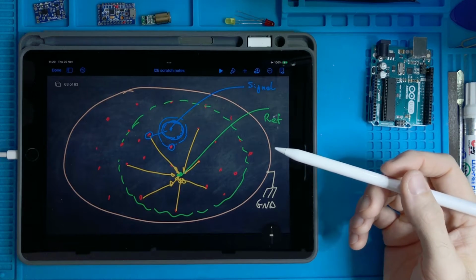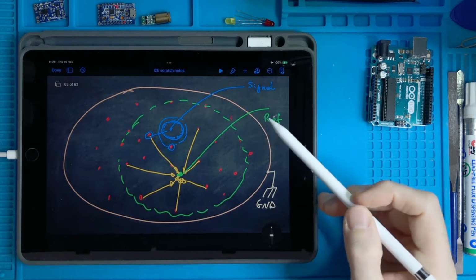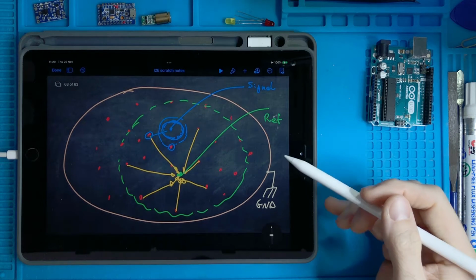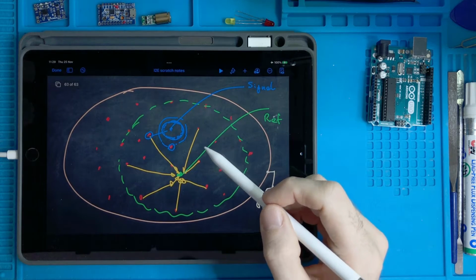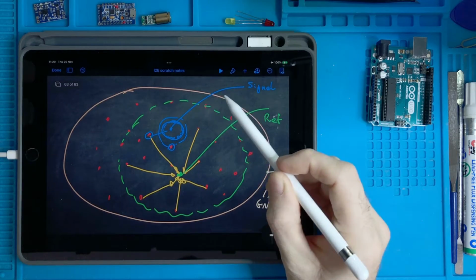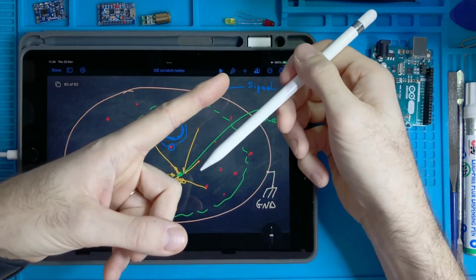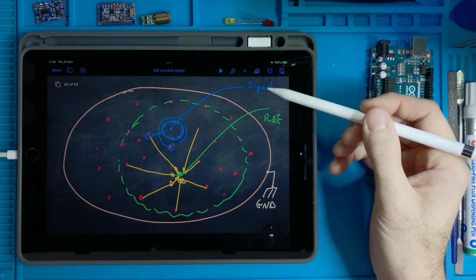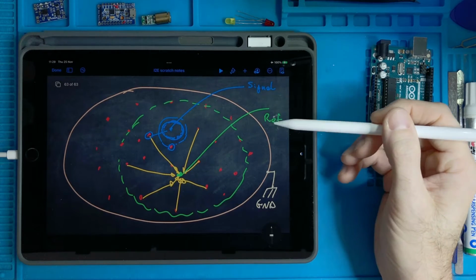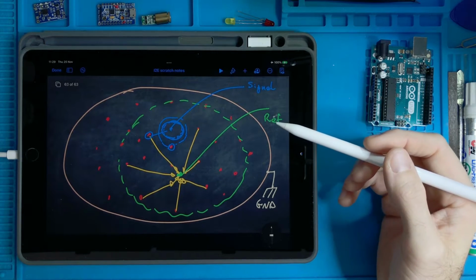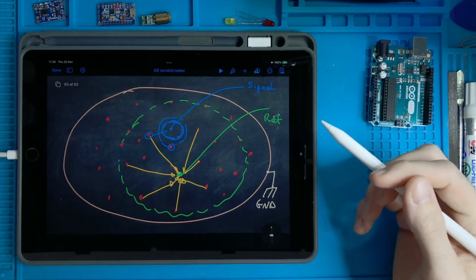And then, secondarily, if you connect the reference directly to ground, you don't have the case that those two electrodes, the green one and the blue signal one, are close to each other, so they are not picking up almost the same noise. And if they don't do this, then when the differential amplifier takes the subtraction, you will not get noise cancellation.